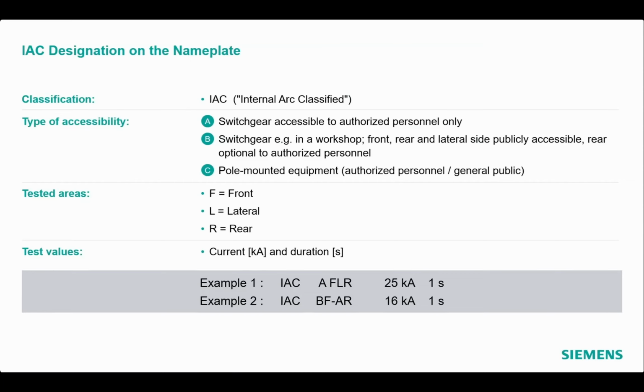In the example 1, IAC AFLR 25 kA 1 second, one can refer to a switchgear which is internal arc classified with accessibility to authorized personnel on the front, lateral, and rear sides, and tested with a current of 25 kA and duration 1 second. In the example 2, IAC BF AR 16 kA 1 second, the switchgear is internal arc classified with front accessibility to public and rear accessibility only to authorized personnel and tested with a current of 16 kA and duration of 1 second.